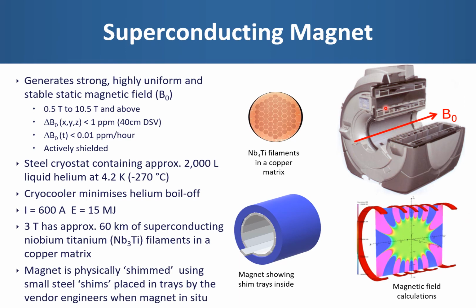Older magnet designs typically contain around 2,000 litres of liquid helium, with newer designs coming onto the market now which probably only require around 7 litres. Helium is created as a byproduct of radiation decay, so it is mined in a few places around the world. It's a non-renewable resource and therefore currently quite expensive per litre. But as mentioned, the cryocooler helps to minimise the boil-off, and most magnets these days are claimed to be effectively zero boil-off.